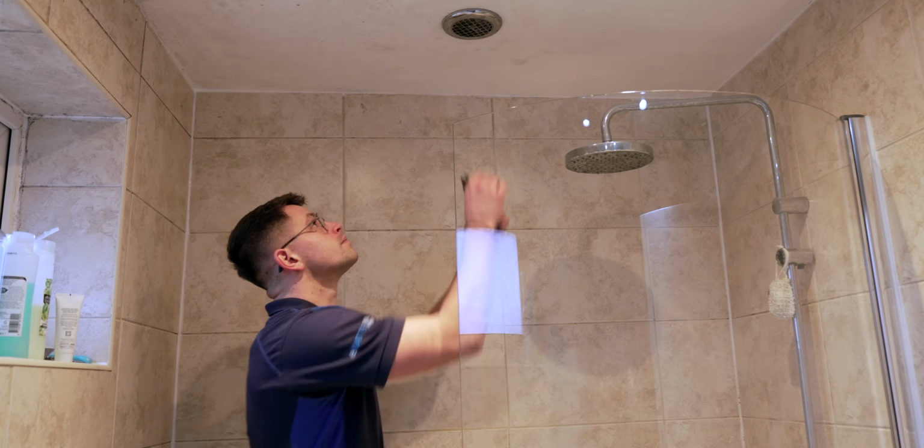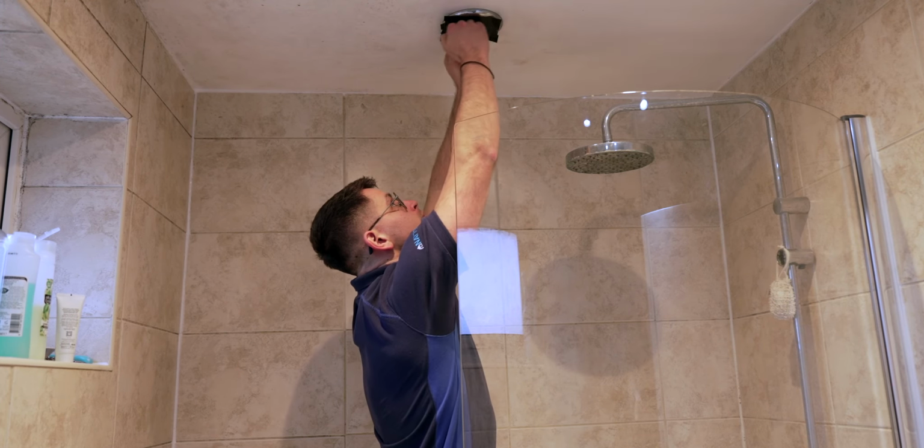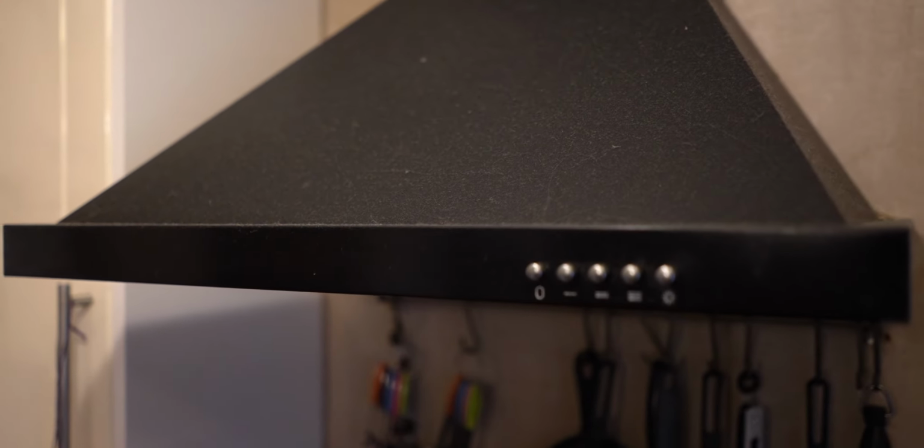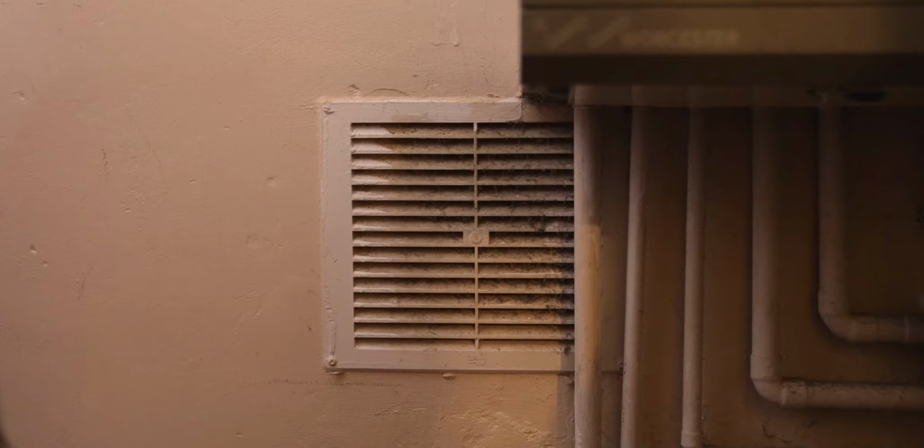It's a really good point. One thing that we're measuring with the air permeability is uncontrolled ventilation. Right. Yes. That you might not know about at all. Exactly that. So things like extractors, we actually tape them up for the test. Right. So normally you have trickle vents on windows, extractor fans, vents for boilers. Obviously you don't seal those up. And cookers and all that sort of thing. Yeah.